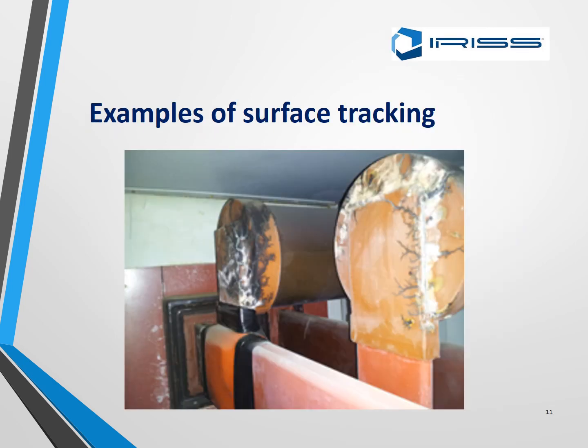Here are examples of surface tracking. As you can see on these busbar joints, not only is there white powder but there is also tracking. It looks like a tree or leaves — that is the carbon — and that is the partial discharge now starting to eat away at the metal.